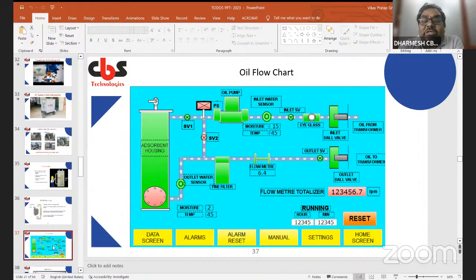This is the oil flow chart. Oil comes from the transformer through the inlet valve, then the eyeglass, then the inlet solenoid valve, which you can check is NO. Then there is the inlet water sensor, where you can see moisture is 15 and temperature is 45 degrees.